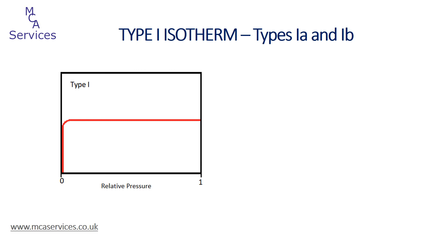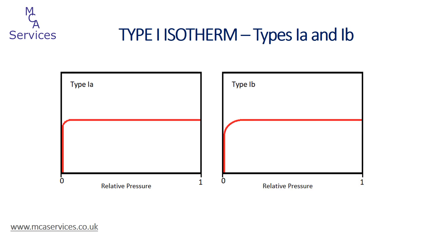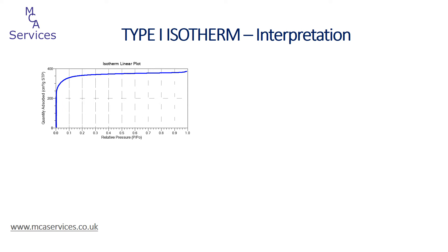The classic type 1 isotherm becomes the type 1a isotherm, whereas the type 1b isotherm has been introduced with a broader isotherm knee due to the presence of larger micropores and the extension of these into the distribution of mesopores. This is an isotherm from nitrogen adsorption on an activated carbon sample measured here at MCA Services. With type 1 isotherms we work just from the adsorption data. In order to reliably collect data at extremely low relative pressures, we don't just need to measure the corresponding absolute pressure accurately but need to generate these pressures with very high stability over quite long time periods.